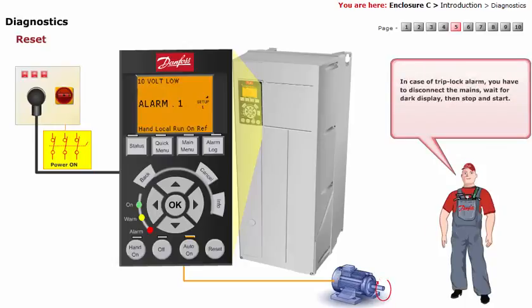In case of trip lock alarm, you have to disconnect the mains, wait for dark display, then stop and start.